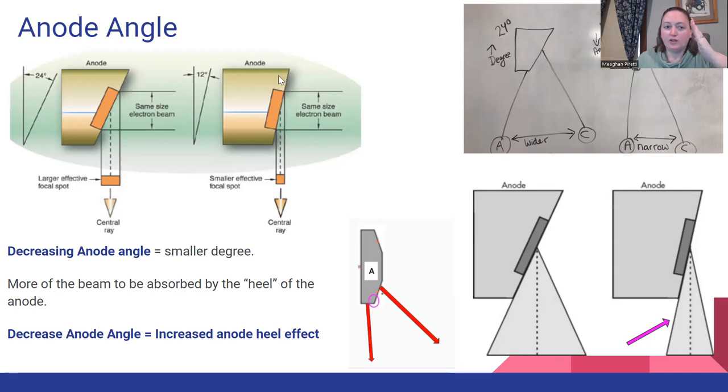A larger anode angle like this one over here kicks it back more and opens up this area here. By decreasing anode angle, so the smaller degree, we are increasing the anode heel effect. Why? Because the heel is more in the way.